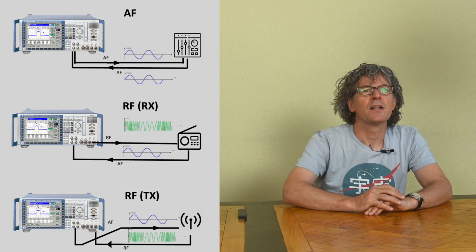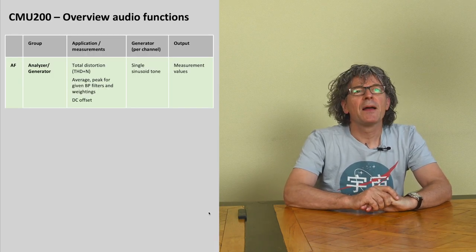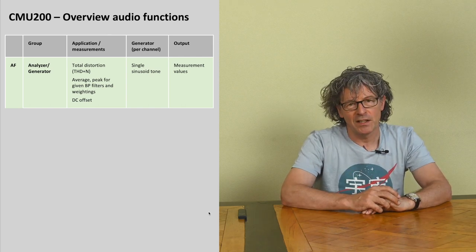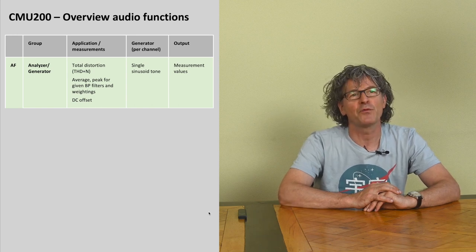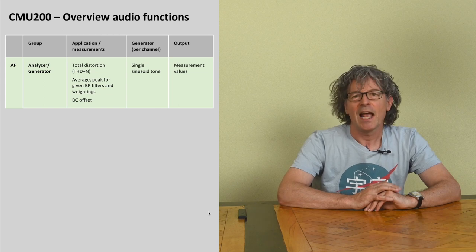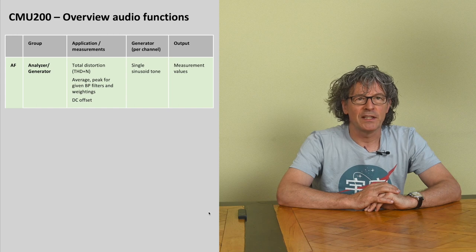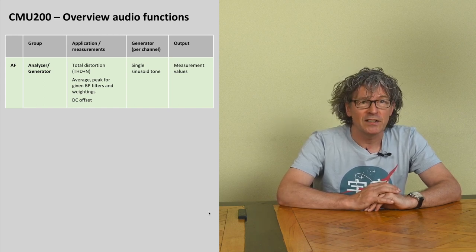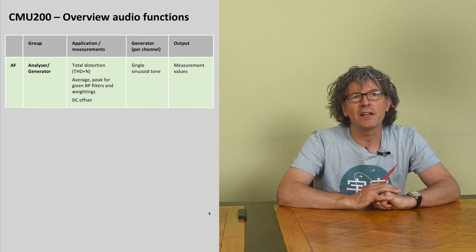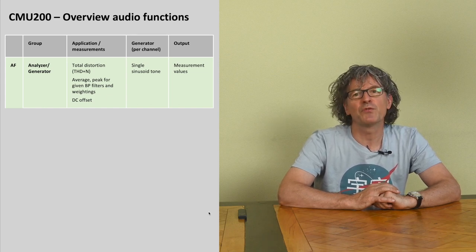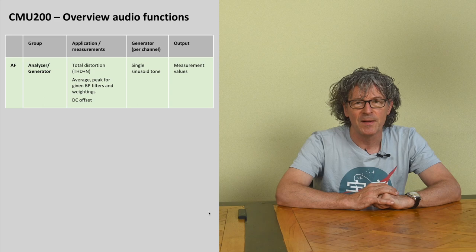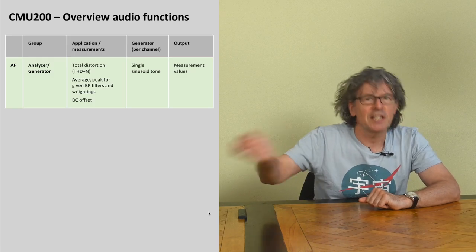Let's quickly review the audio measurement functions — or groups, as they're called in the device. I'll stick with the terminology Rohde & Schwarz uses. The first is simply called Analyzer/Generator: these are basic measurements on an audio device. You measure total harmonic distortion plus noise (THD+N), signal strength like RMS average or peak signals, and you can use different bandwidth filters and audio weighting patterns. You can also see the DC offset of your device. The generator puts out a single sine tone and whatever comes back is measured.